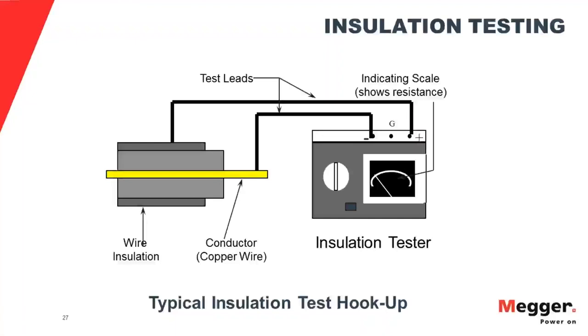Note that the industry standard is negative to circuitry, positive to the return. And you will see that very often in SOPs. Now, the scope of this particular talk doesn't go into that. You can always contact me and I can explain it in more detail. The main point here is that on modern insulation, that really is not critically important. So if you accidentally do testing all day with the reverse polarity, it's not a problem. Don't worry about it. But when you look at SOPs, especially long-established SOPs, you will constantly see negative to circuitry, positive to return. And that's what we show you here.